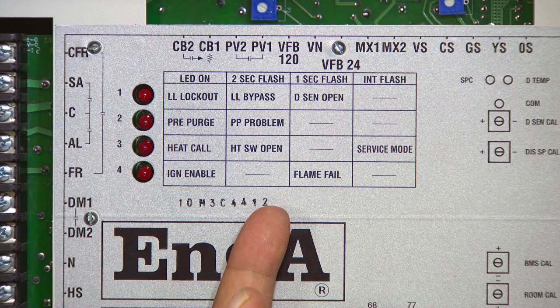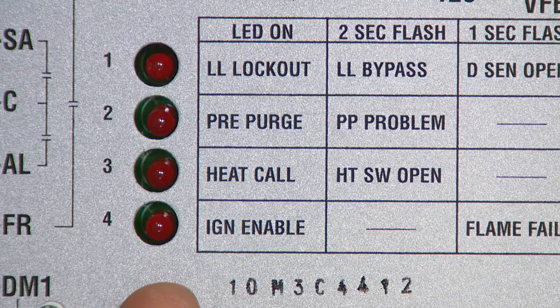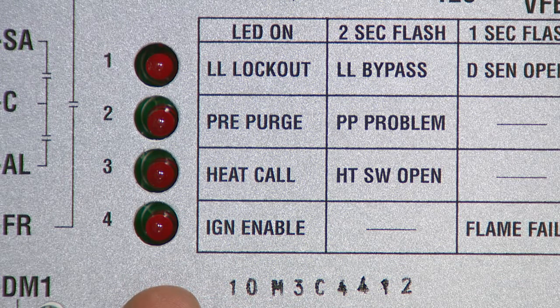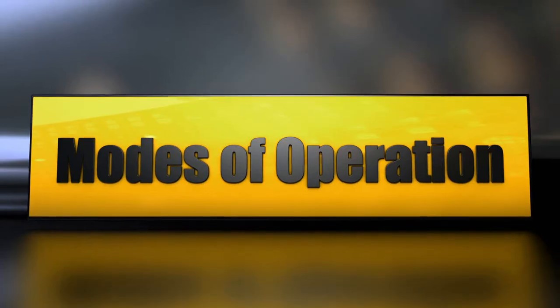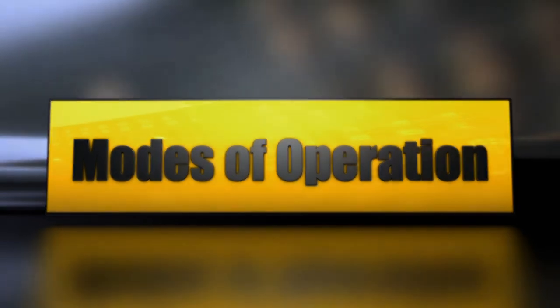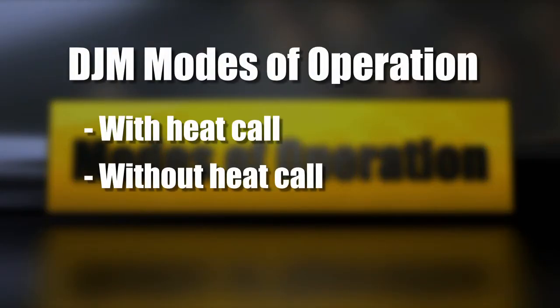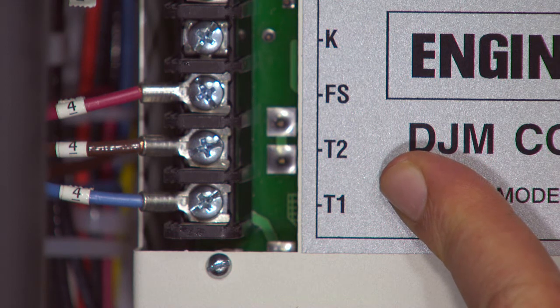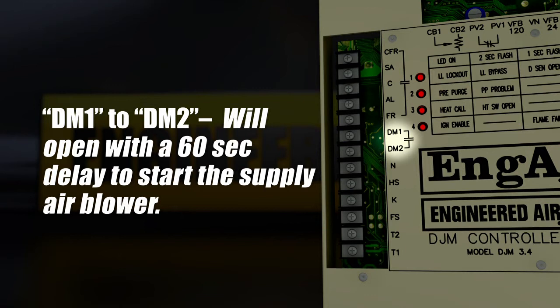The status light information grid allows the service technician to identify the current state of the DJM-3's operation. The 4 status lights have different meanings based on their rate of flash: on, 2-second flash, 1-second flash, or intermittent flash. Now let's move on to the modes of operation. The DJM-3 has 2 distinct modes of operation, one with a heat call and one without a heat call. First, no heat call. Power on to the T1 and T2 terminals for the DJM-3 board with the FS terminal powered will allow the damper motor to open on damper terminals DM1 and DM2, with a 60-second delay to start the supply blower.